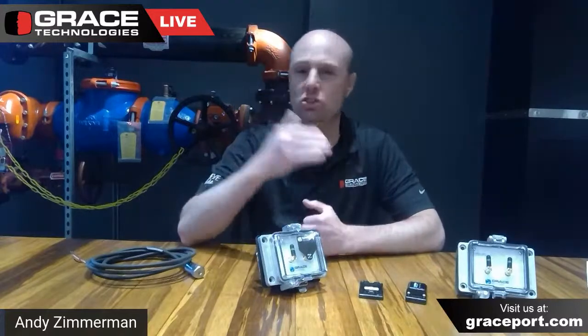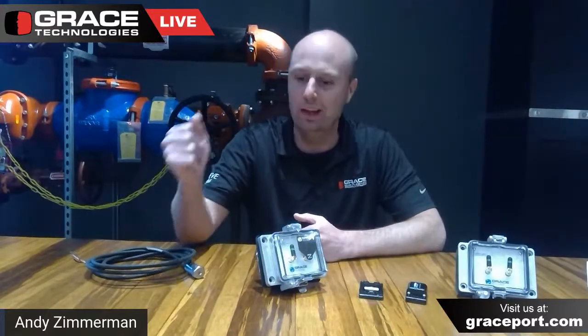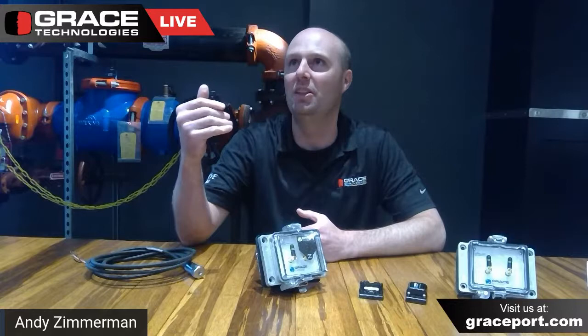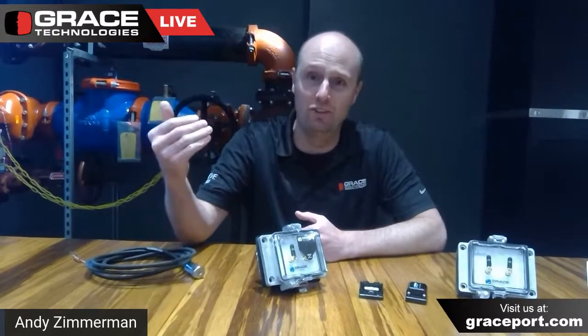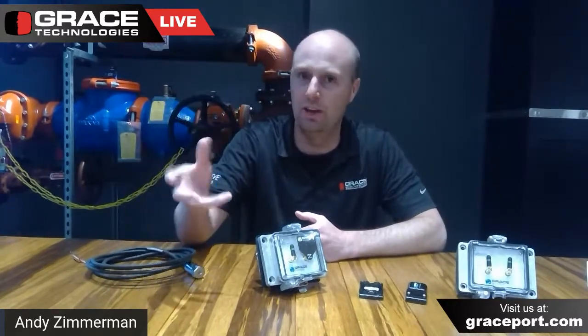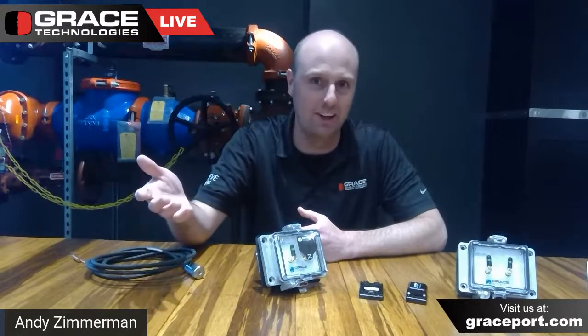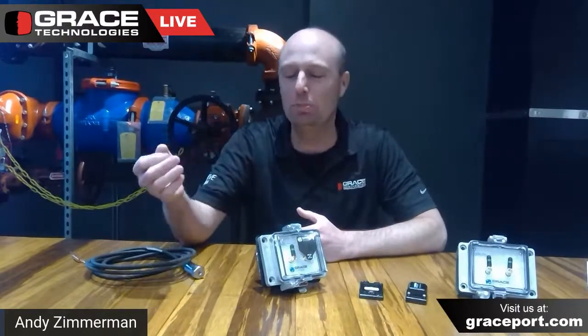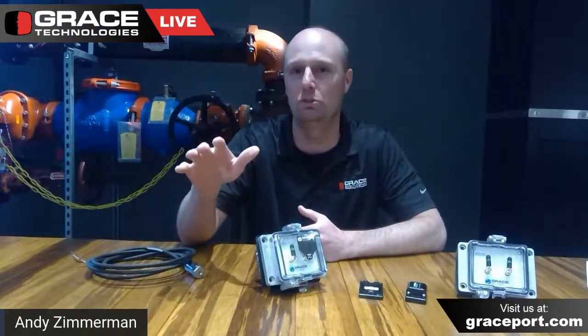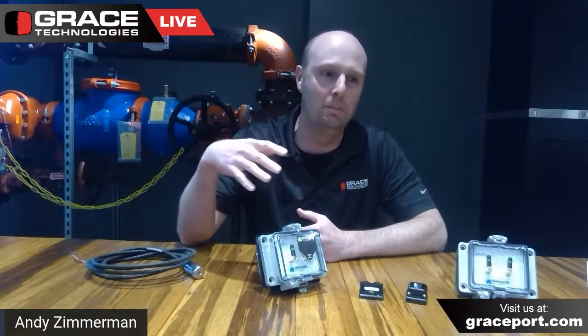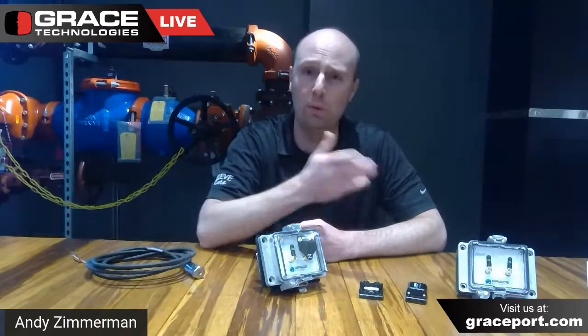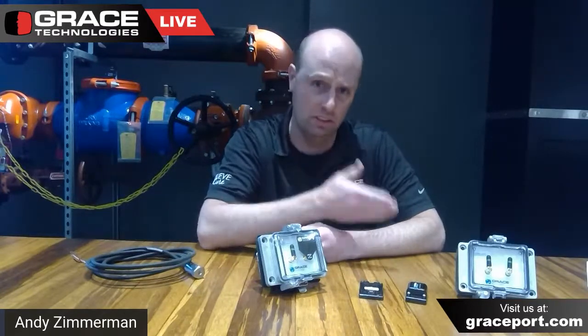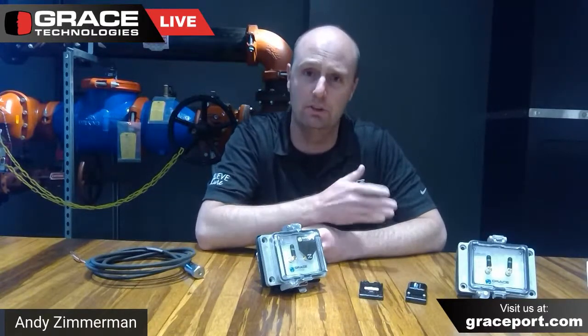To walk you through that quickly: maybe the lowest hanging fruit for detecting failure in a motor or something else that spins is just waiting until it fails. But most people will at least notice something's wrong when it starts making a lot of noise or has an elevated temperature. Even before that, we can use current measurements to give us somewhat of an early indication that something's going wrong.